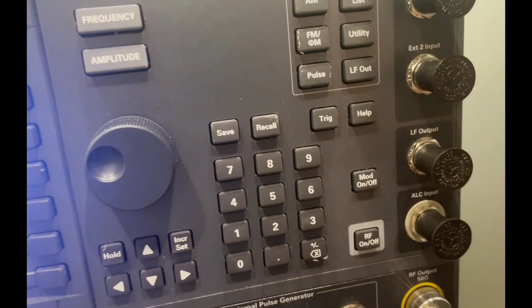Let's go through the process of a complete cal. First, I am selecting Timebase, mainframe user time calibration, and next. Before I continue, the one important thing is that the DCA must be warmed up for 60 minutes so it's stable. And the PSG also needs to be warmed up 20 minutes, 25 minutes before it is stable, depending on the model that you're using. That way you'll get, again, repeatable results.